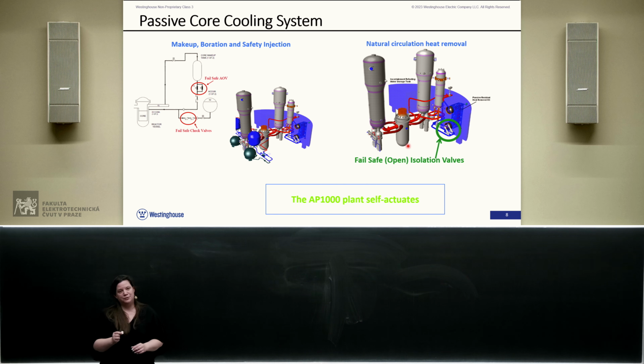First of all, there are many different classes of passive safety systems. The one we're working with in AP1000 is a system on standby during normal operation. It has no function during normal operation and requires a one-time valve alignment to actuate, to start functioning in case of an emergency - an emergency being any accident that my plant could see happening.